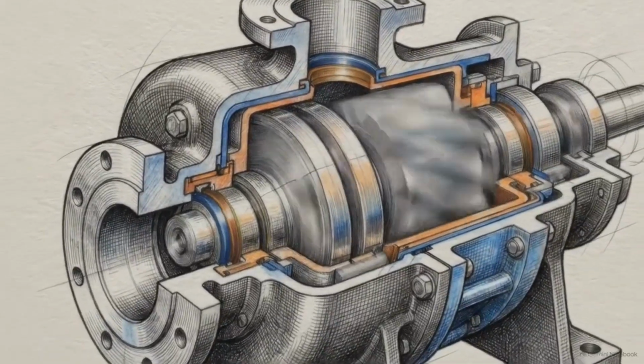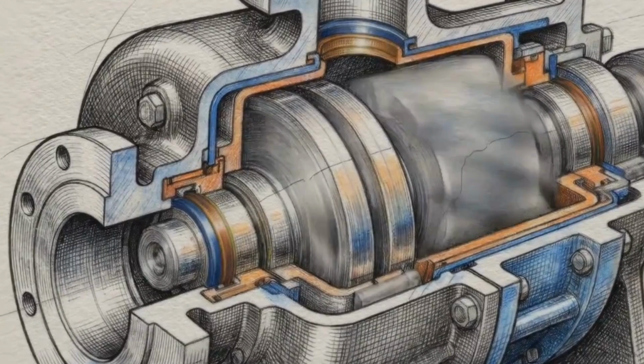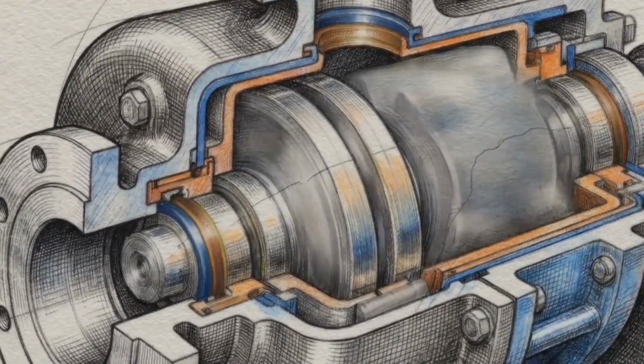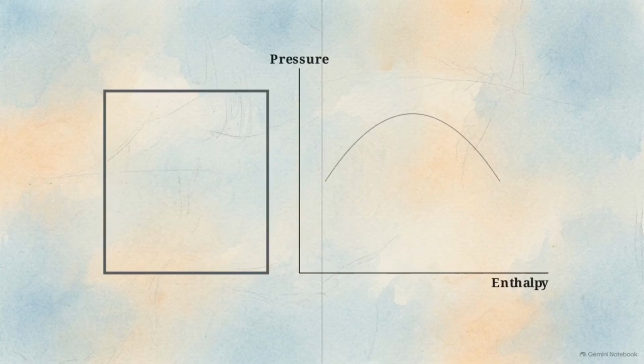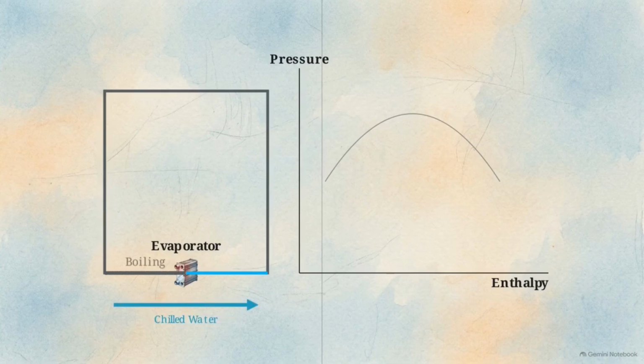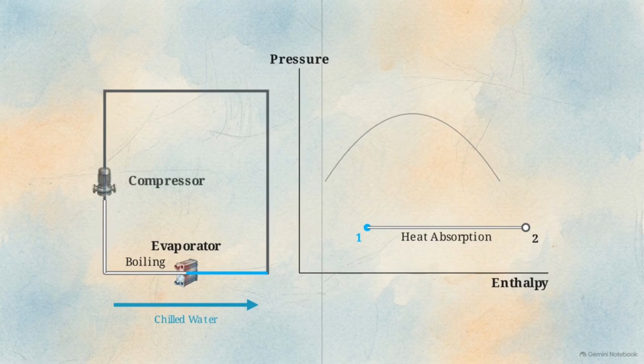To understand how megastructures remain habitable, we have to look at the exact mechanism making this possible: the four-stage vapor compression engine. We start with a closed loop of pipe, isolated from the building's air, containing a chemical refrigerant. We'll map its behavior on a pressure enthalpy chart. The first node is the evaporator, where warm return water interfaces with the refrigerant. The refrigerant absorbs the building's heat, boiling into a vapor and dropping the water's temperature. On our chart, this absorption registers as a direct increase in enthalpy, while pressure remains constant and low.